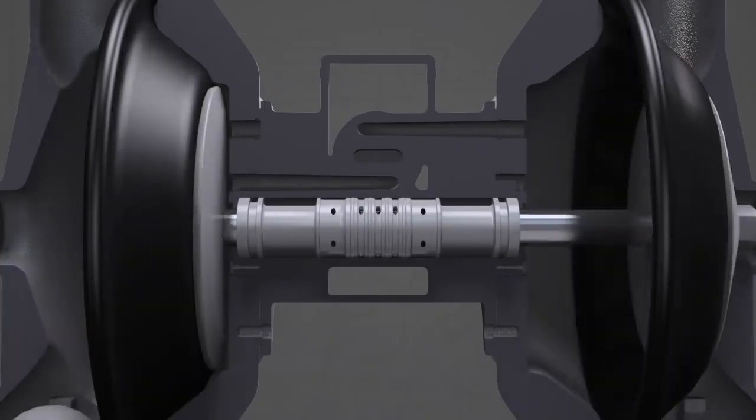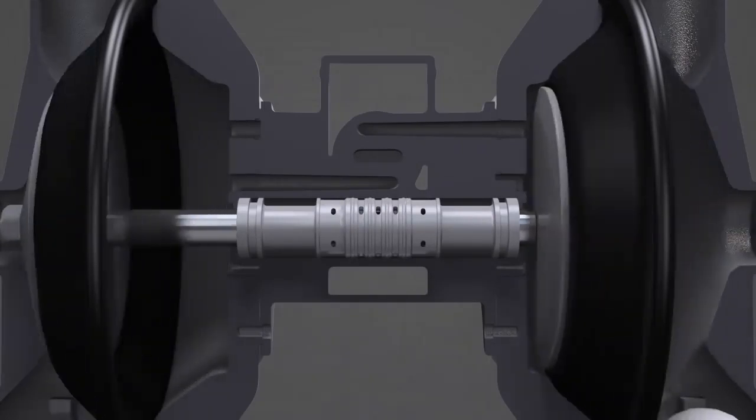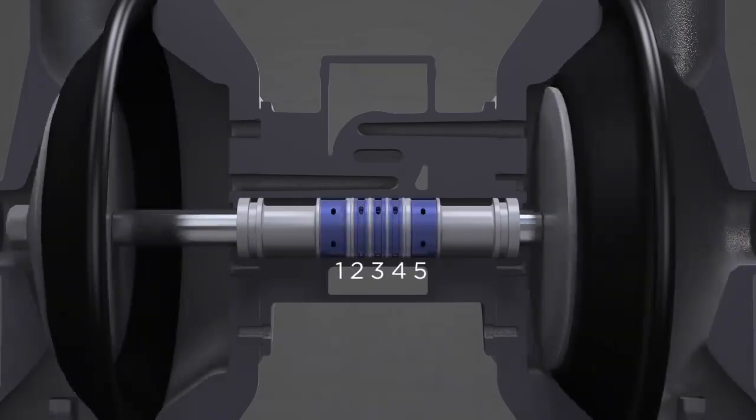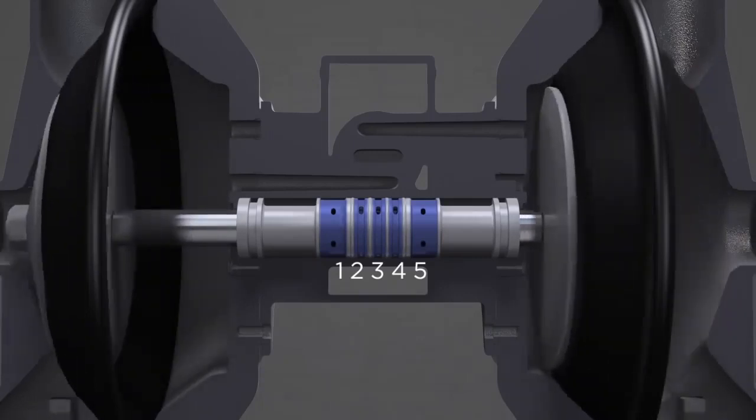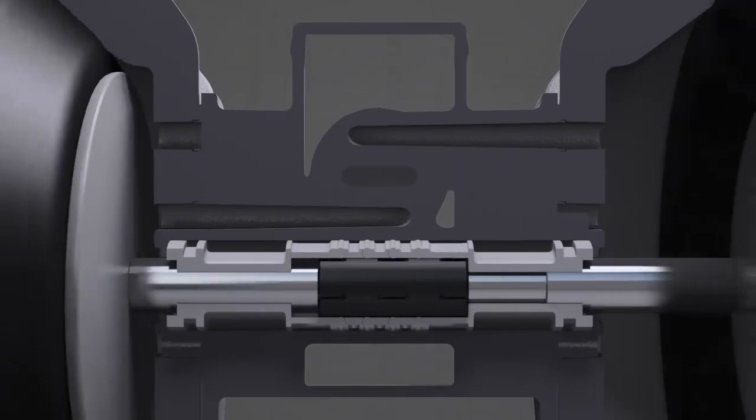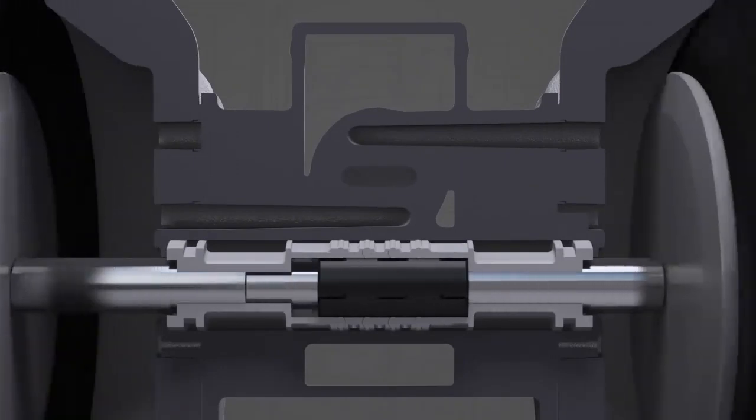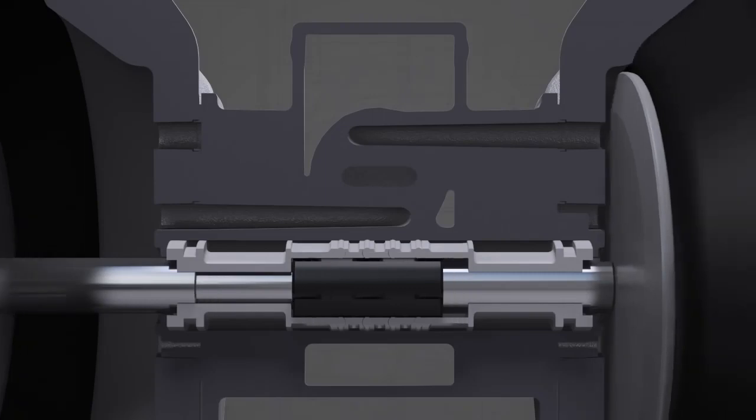The pilot air valve directs the air that moves the main air valve. It is constructed of five separate chambers and a central rod that moves side to side due to the diaphragm pressurizations. The pilot and main air valves work together to drive the pump. The pilot air valve has two logical states, which we will call left and right.